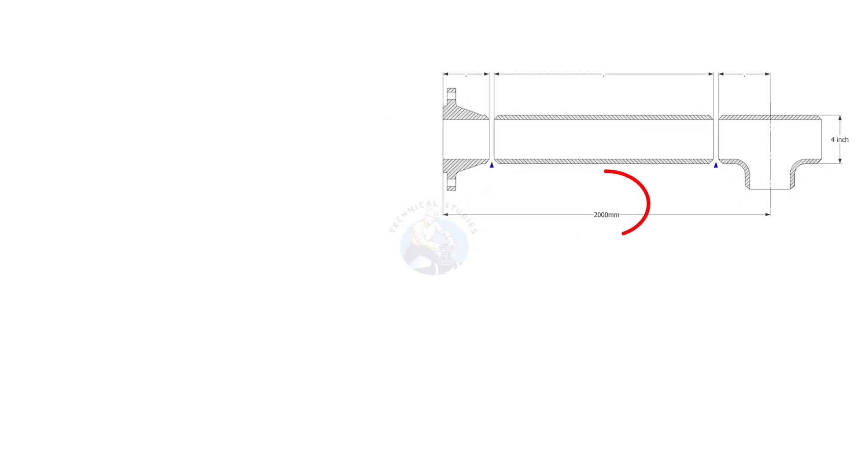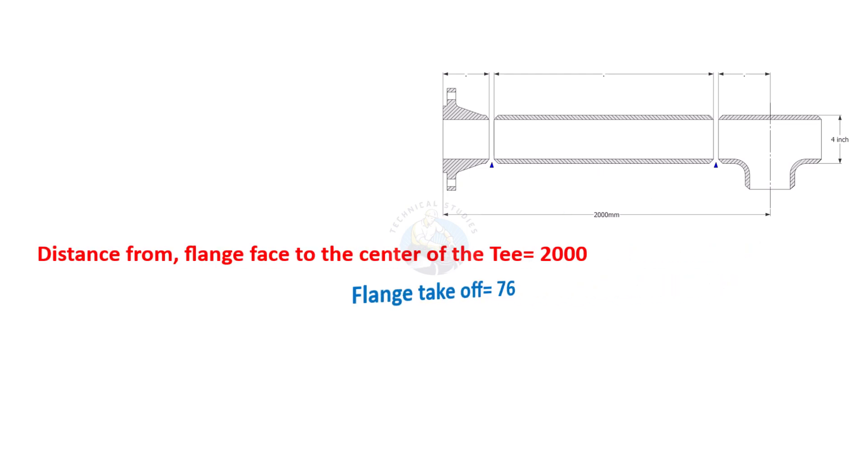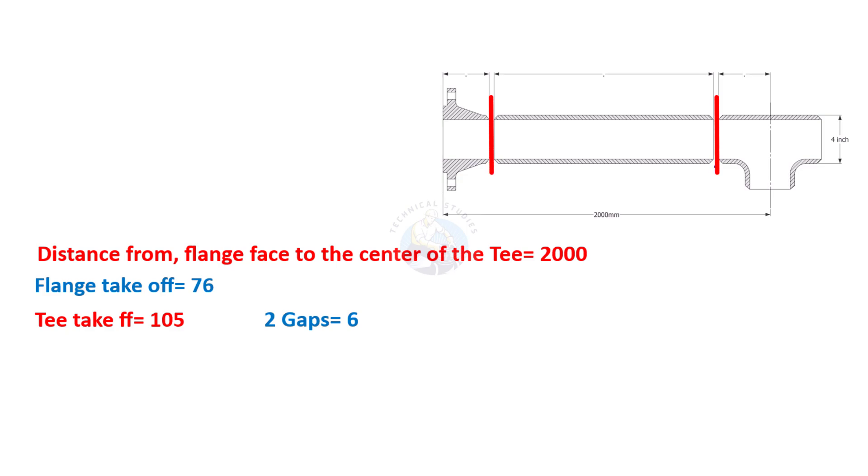Let us calculate. The length from the face of the flange to the center of the T is 2000 millimeters. Flange takeoff length equals 76 millimeters, T takeoff length 105 millimeters, two gaps equals 6 millimeters.